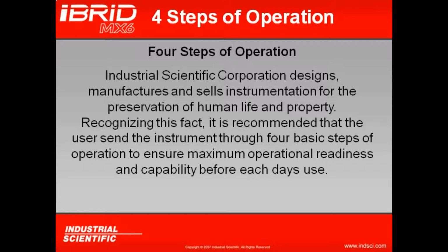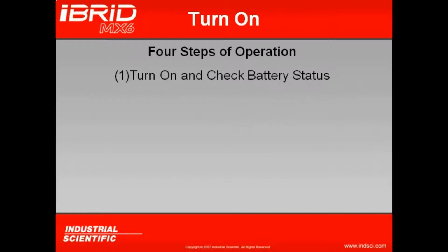With any gas detection instrument, it is always recommended that before you use it, you take it through the 4 steps of operation. Industrial Scientific Corporation designs, manufactures, and sells instrumentation for the preservation of human life and property. Recognizing this fact, it is recommended that the user send the instrument through 4 basic steps of operation to ensure maximum operational readiness and capabilities before each day's use. The first step of operation is always to turn on the instrument and to check the battery status. With this, we're also going to ensure that the proper sensor configuration and the proper sensors are installed in the instrument for the job at hand.